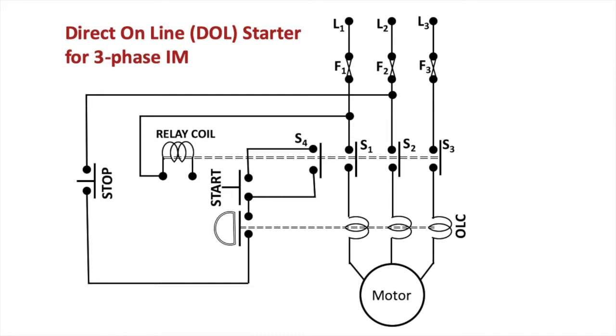So the first one is the DOL starter, which has its limitation: it can't be used for a motor rated above 5 kilowatts. If a motor is rated below 5 kilowatts, the best suited starter is the DOL starter. The DOL starter has a few basic protections along with the starting part. It doesn't have any methodology by which we reduce the current, but it has the overload relay and the no-volt relay. These are the two functions integrated with the DOL starter.